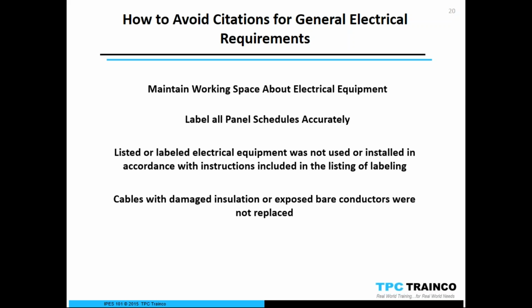So cables with damaged insulation or exposed bare conductors not replaced. And believe it or not, I do see this quite often, that there'll be some maybe 500 kcmil metal just hanging from the ceiling, and they're all energized. And I said, why do you have those? Oh, in cases of emergency, this is our backup power. Well, that just can't be. We've got to make sure that because of shock, arc flash, arc blast, these cables are intact and ready to go.